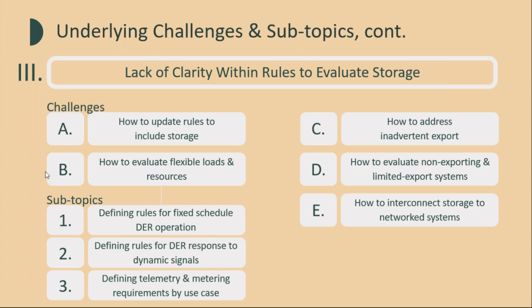Storage can export to the grid, but that doesn't mean every system is designed to do so. Whether a particular storage system exports depends on the desires of the customer, how the system is designed, and various other factors. But again, as with the import and export issue, very often the screening or study process assumes that export will occur or otherwise imposes unnecessary requirements, which can increase the cost and time of interconnection.